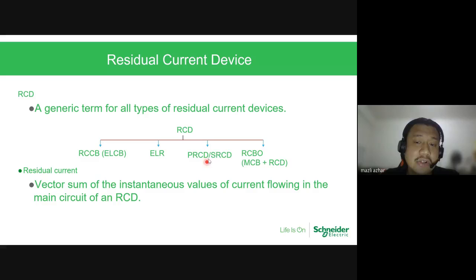Portable residual current device or socket residual current device, which you can see on the labs, or portable when you buy a very expensive extension socket, whereby they can say they are protected with RCCB or ELCB. Then you will have RCBO, MCB plus RCD. So in electrical terms, residual current means the vector sum of the current flowing in the main circuit of an RCD. So when you say vector sum, if you divide it into 5, the total must be the same as the incoming power. So it's very simple. Whatever goes to the load must come back at the same value.